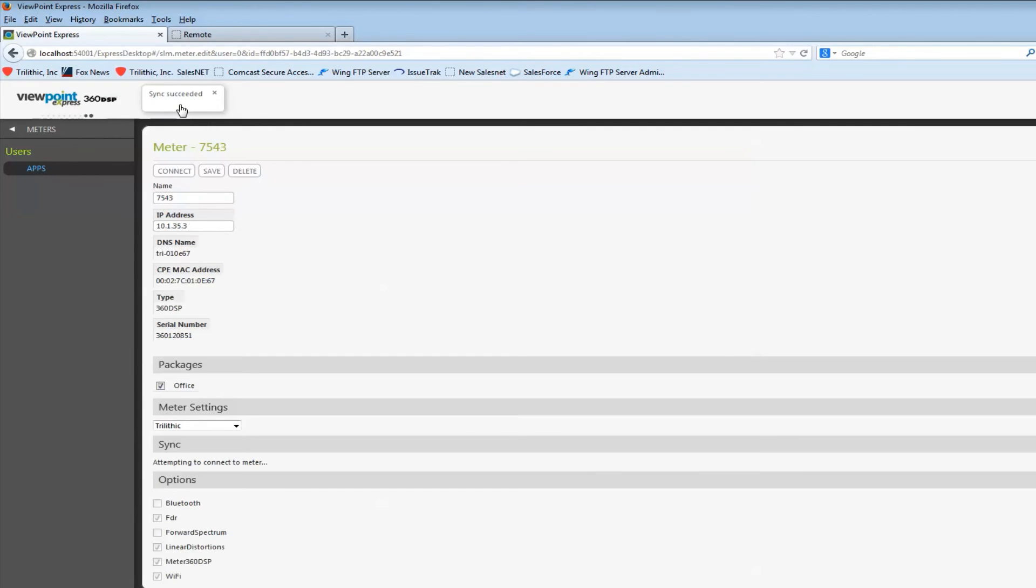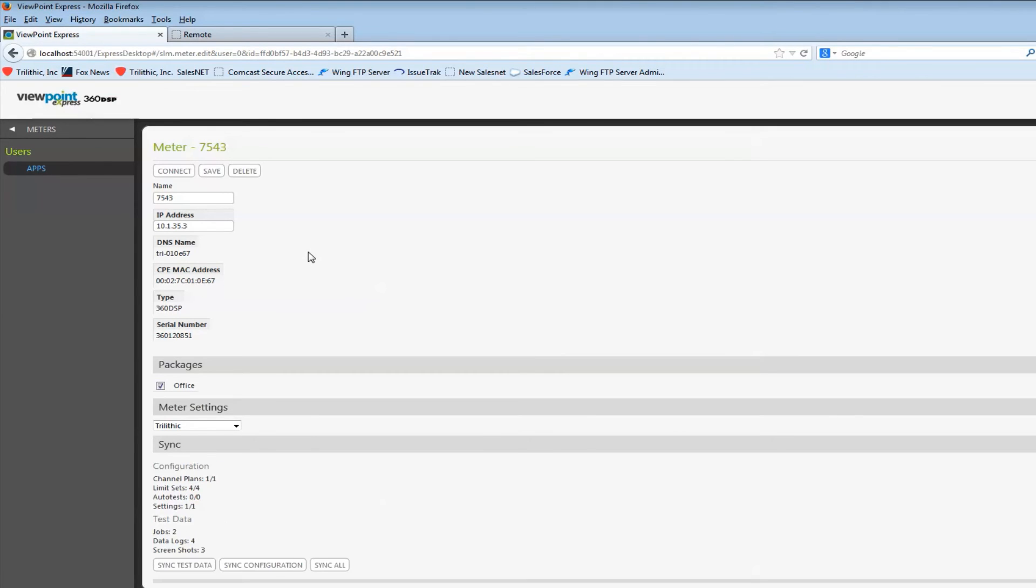Sync succeeded is what we're looking for. And what I've just done is very quickly transferred all of those channel plans, limit sets, auto tests, meter settings, and the security settings into my 360.